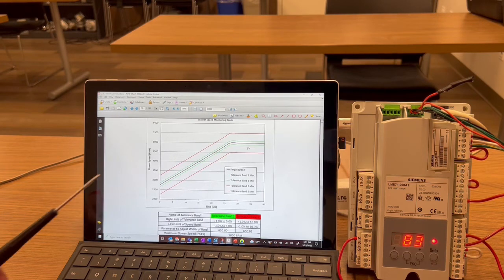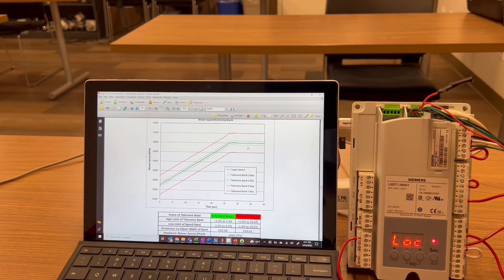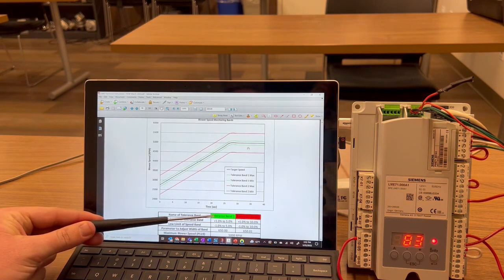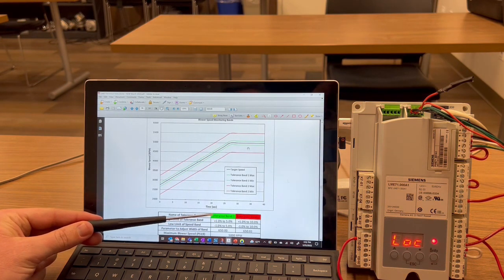If it falls outside of that band for five seconds, it will cause a speed fault. Tolerance band two is if it falls outside of that band, it will immediately shut down. These tolerance bands are adjustable. Parameter 650.00 is for tolerance band one with the time element associated. Tolerance band two is 650.01.